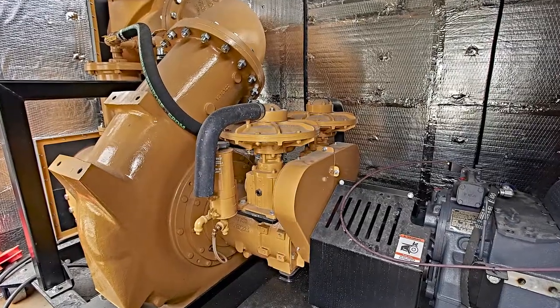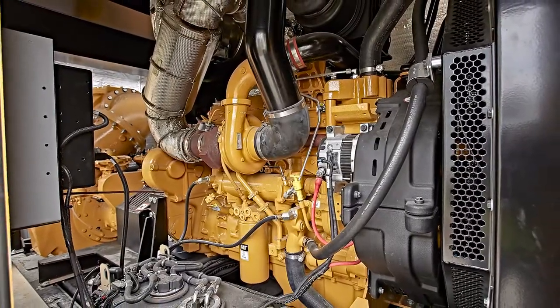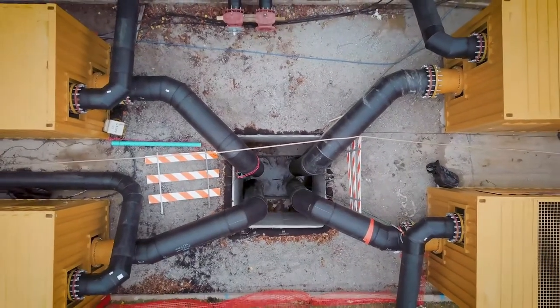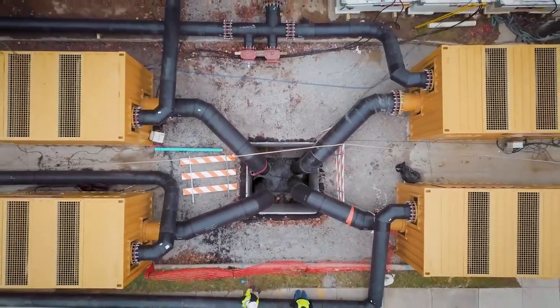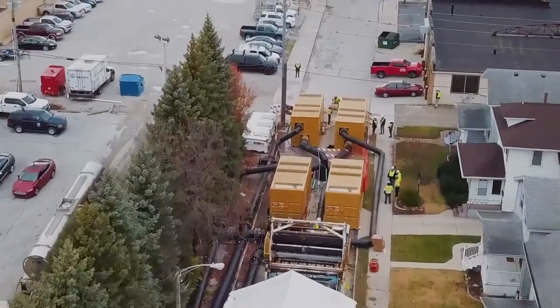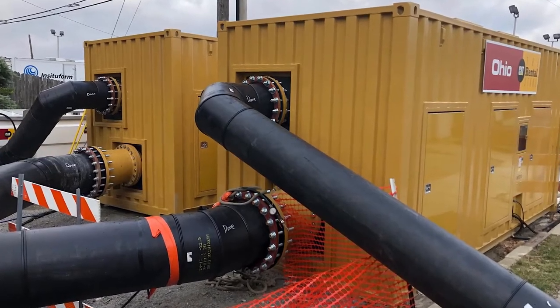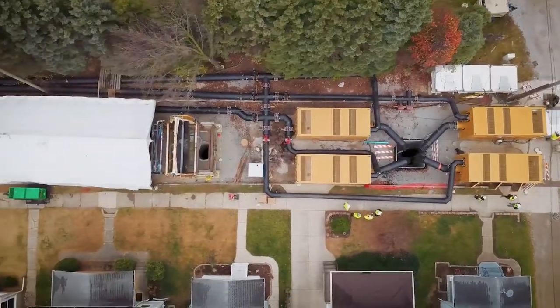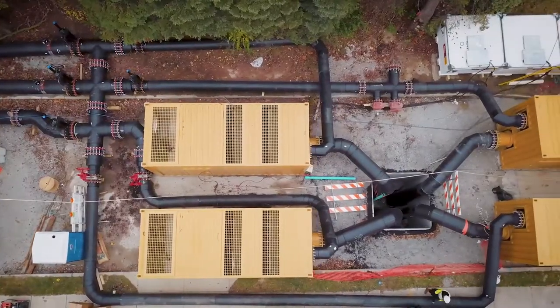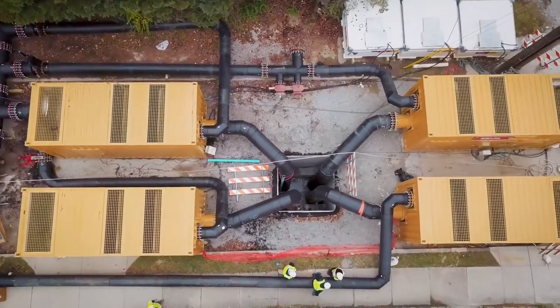Pairing the Pioneer Prime 18-inch vacuum-assisted standard centrifugal pumps with Caterpillar C13B engines, Franklin Electric designed and built four diesel pump packages, each engineered to handle 10,800 gallons per minute and pass heavy-duty solids. The packages were engineered with sound-attenuated enclosures that met the residential noise level rating of 69 A-weighted decibels to reduce noise for residential homes within 20 to 30 feet of the pumps. Franklin Electric also designed a skid platform that could be rolled out of the enclosure, providing easy access for routine maintenance and inspection.